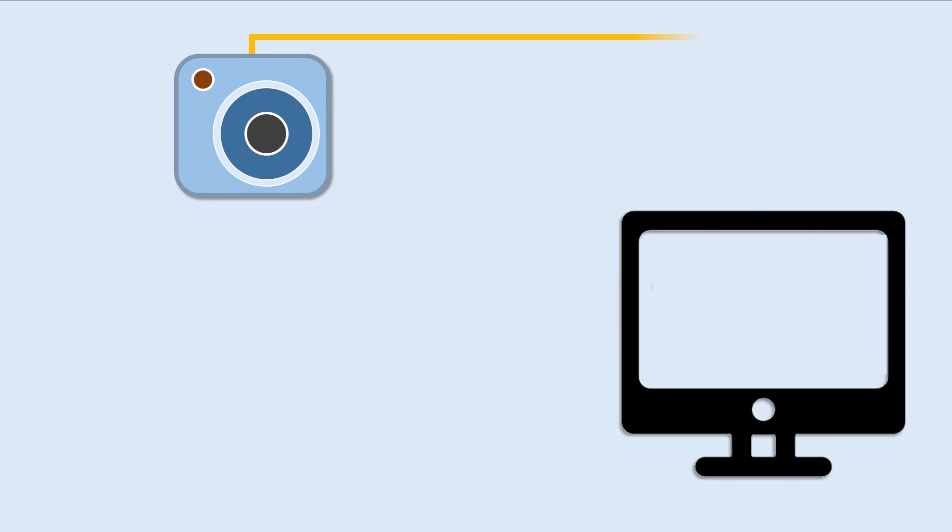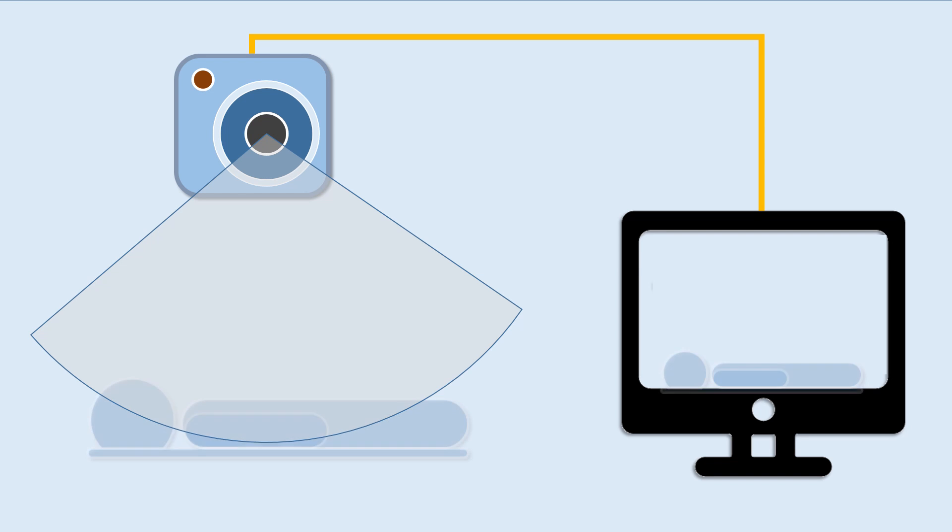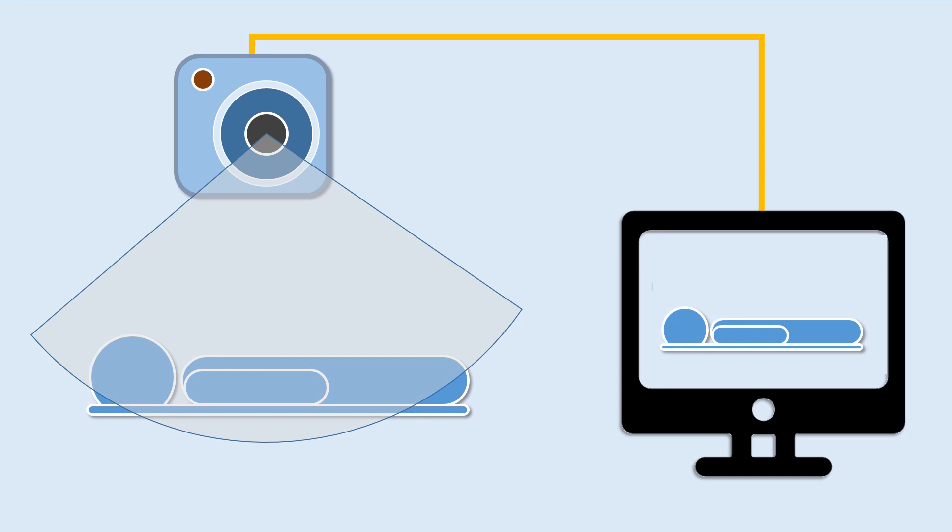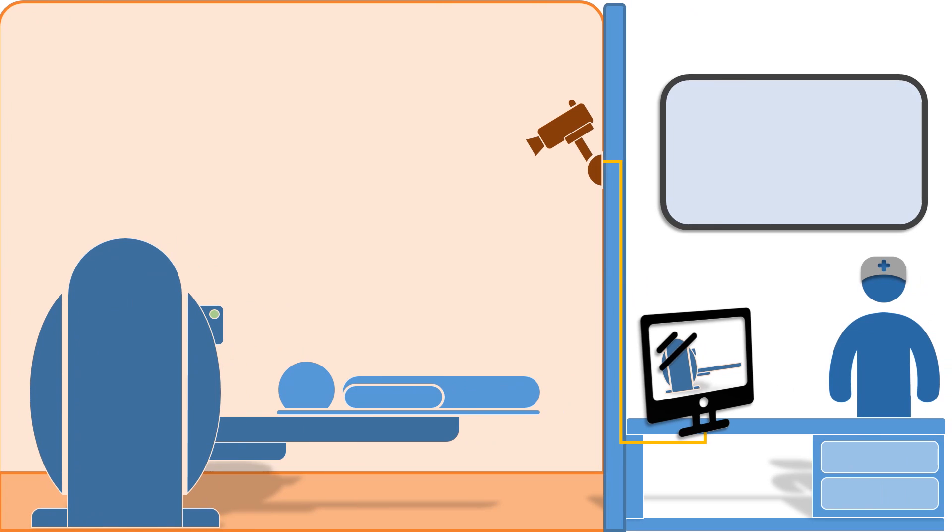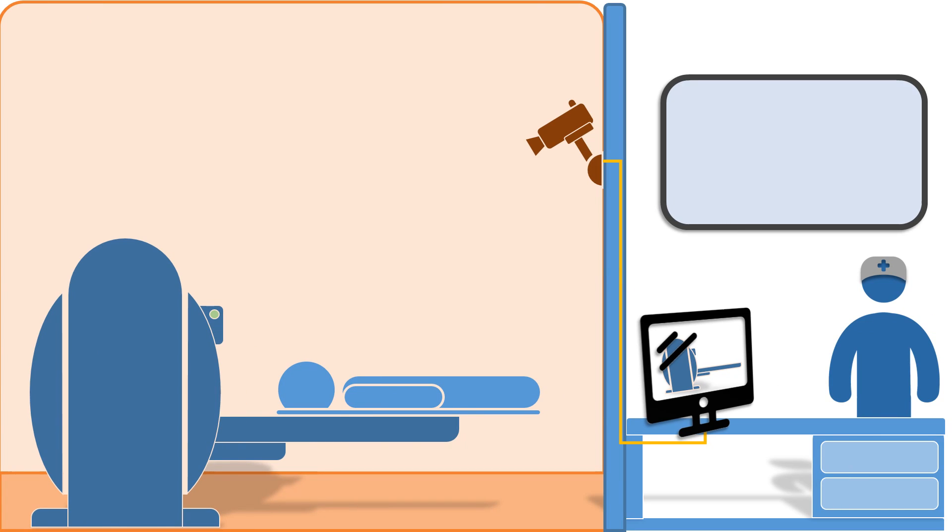The SAMMD is pretty simple. It consists of a camera connected to a computer. The camera watches and displays the patient, and when that patient moves, the system alerts with an audio and visual cue. By combining high-fidelity cameras with sophisticated software, the SAMMD can catch motion artifacts before the technologist.